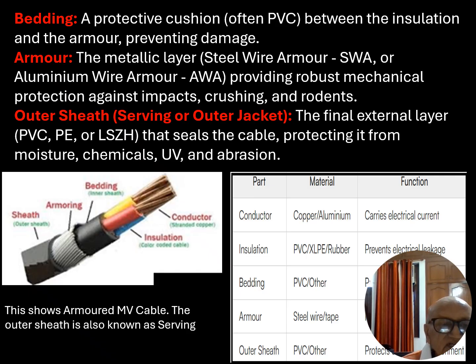Friends, we are discussing the various components of the cable. Apart from the conductor and insulation, the cable has got bedding, a protective cushion, often PVC, between the insulation and the armor preventing damage. This is also known as inner sheathing. Armor, the metallic layer, steel wire armored, SWA, or aluminum wire armored, AWA, providing robust mechanical protection against impacts, crushing, and rodents.